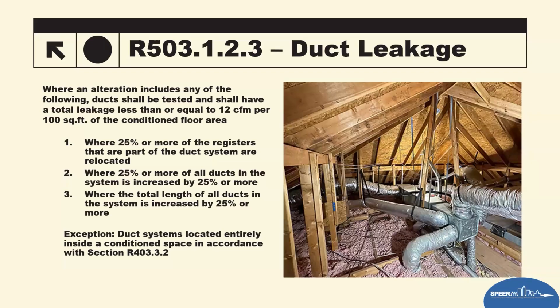And then, of course, duct testing. Anything that's 25% or more of registers have been replaced, 25% or more of all ducts have been replaced, the total length of ducts been increased by 25%, you can require a duct test to be done. I think there's one city in North Texas that actually does require that on all of them that have a permit that's pulled. But it's 12 CFM per 100 square feet, not the new requirement of 4 or 6. It's going to be 12.